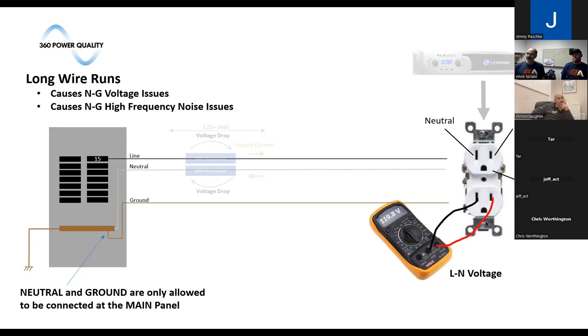So what happens is, when you put a high current load on that outlet, current flows through the line side, and the return path is through the neutral side. If that wire is really, really long, you're going to get a lot of extra resistance. And if you measure the voltage across line to neutral, you'll actually get a voltage there, right? So this is one way that you get neutral to ground voltage.